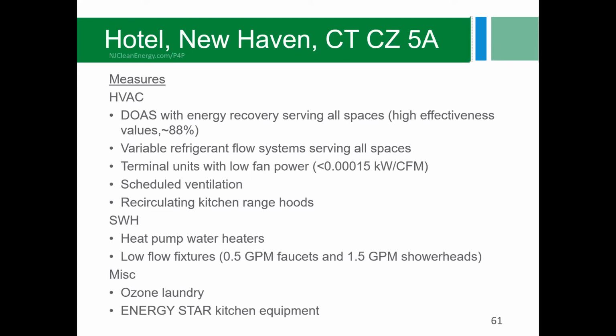It had VRF, variable refrigerant flow systems, serving all spaces in the building. Very low fan power on the terminal units. And like we talked about before, the terminal units cycled with load. The fan power was less than 0.15 watts per CFM.